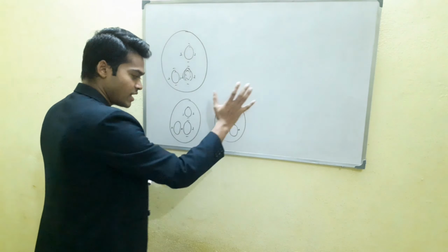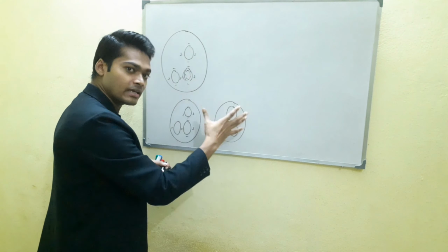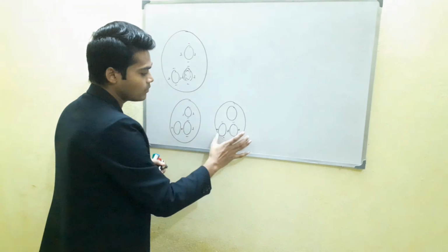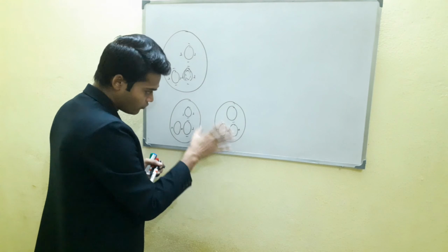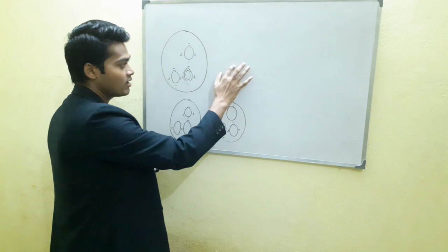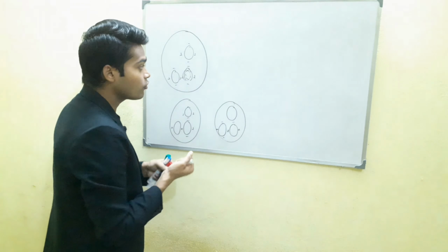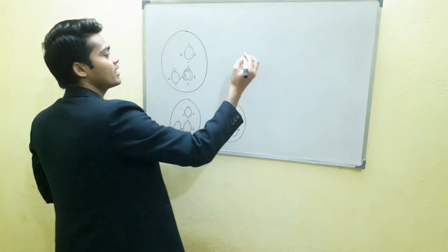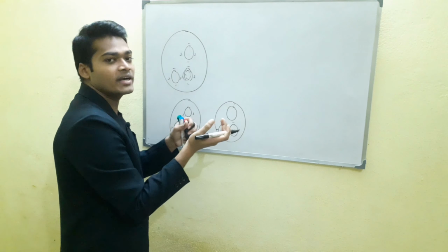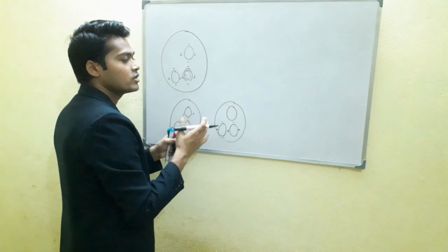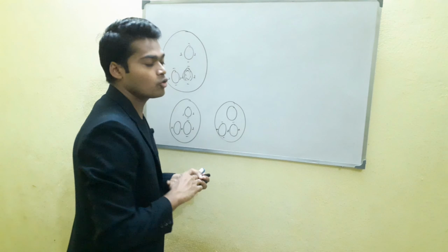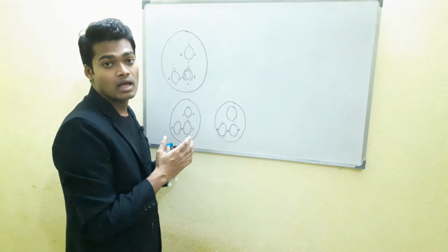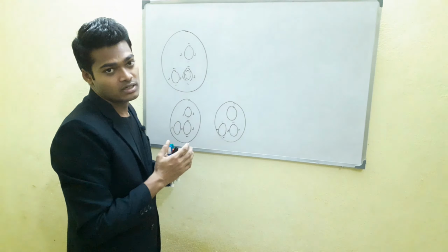Now, is this the actual scene which I observe inside the keratometer? Yes, but before considering this picture, we have one step to focus or align all these things. What are these things? We first align the astigmatism. Why? Because the function of the keratometer is to objectively find the curvature of the cornea, the shape of the cornea, how much astigmatism is present, right?